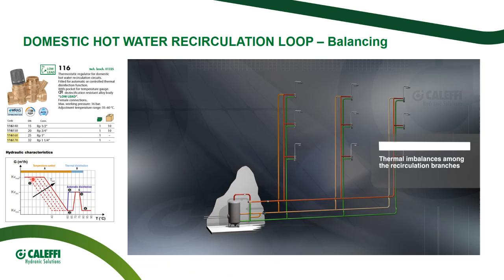So this is the hydraulic characteristic chart of the Caleffi thermostatic balancing valve. You see that every single line is a presetting value that you can decide on the knob. When we are very far from the set temperature, the Kv of the valve is the maximum possible, so the valve is completely open. But the more we get close to the set point, the Kv is reduced up to a minimum value, and this minimum value is the minimum recirculating value. DRVs are always here, so they always supply the system the maximum possible flow rate, and this is an energy waste.